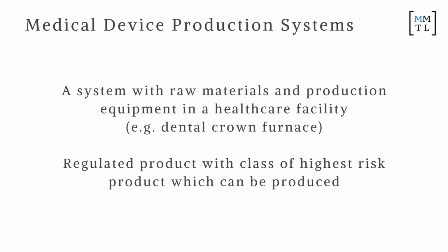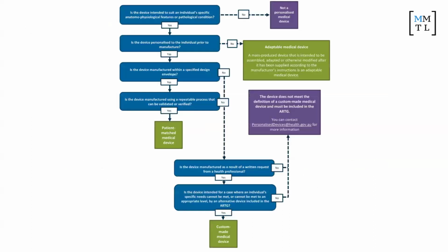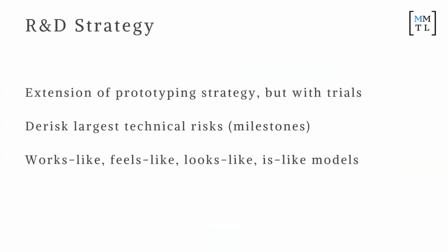So when can you avoid TGA approval? It's usually when fewer than 5 things are being made of something which is patient matched. I don't know if you would ever want to be in that situation. But beyond that, you do need TGA approval for most 3D printed products. This is a flowchart that you can find on the TGA website that covers what we went through, which is whether your device is something that is TGA approved. So again, something to be aware of if you ever do decide to do research in this or you want to actually provide it to a patient.